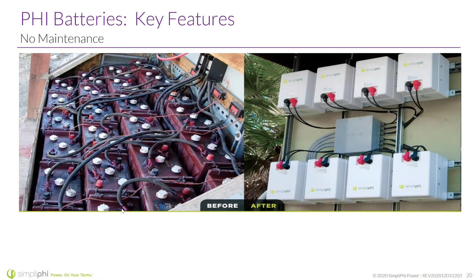Full disclosure, I'm going to switch over this picture probably after this presentation. This battery is now in a white enclosure—you'll see what that looks like, but it's no longer in this black ABS case, it's in a white metal case. It's added maybe a couple pounds, not much though, and it's just stronger and can hold temperature better. So we've switched over to the metal cases even on the standard Phi battery. You're not going to see these black case batteries anymore. Don't fret if you have these in the field and you're worried about expansion—the new white metal case can still be added to this. It just cannot be bussed with bus bars directly to the black ABS cases.